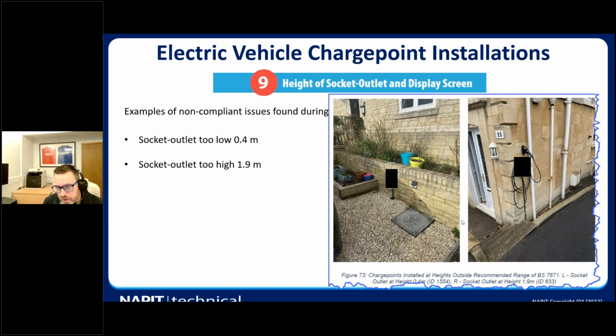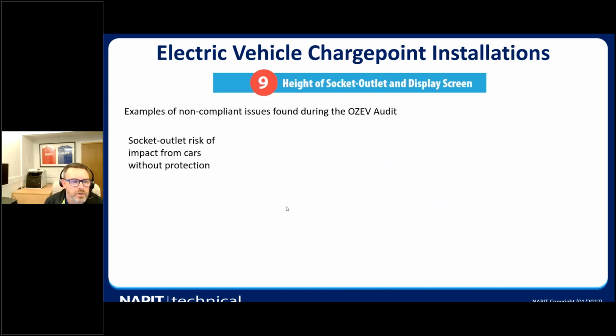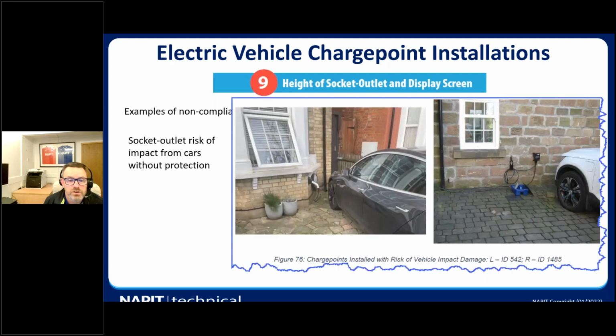There could be some issues on access to plug in as well for some of the points, and potential damage to the cables, things like that. And some other examples where there is a risk of impact on sockets, where they've not been provided with protection to prevent that impact. This socket at low level again may be subject to damage from this car going in here. On the right hand side has got exactly the same point. The car can come in contact with the socket outlet itself.